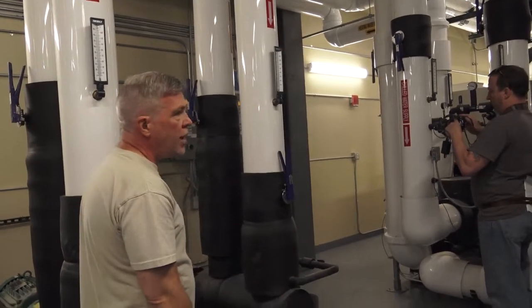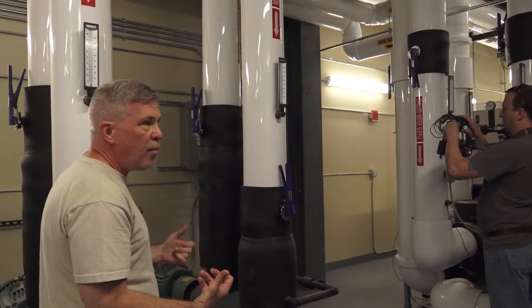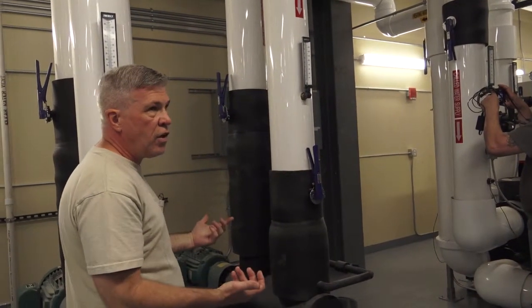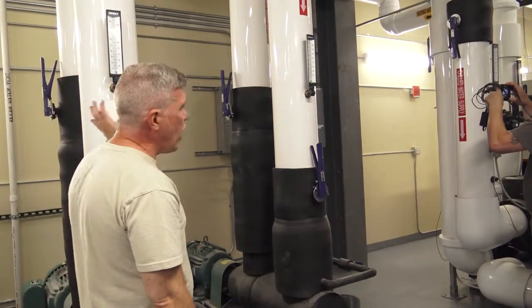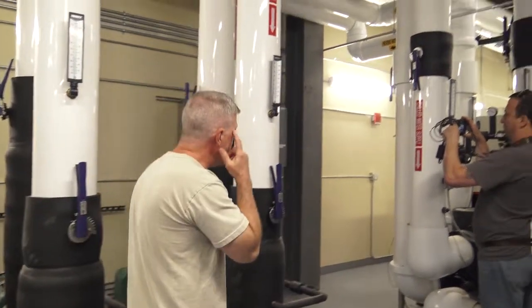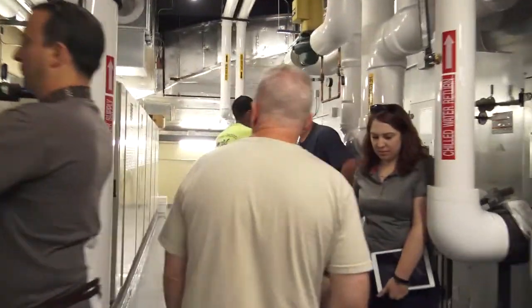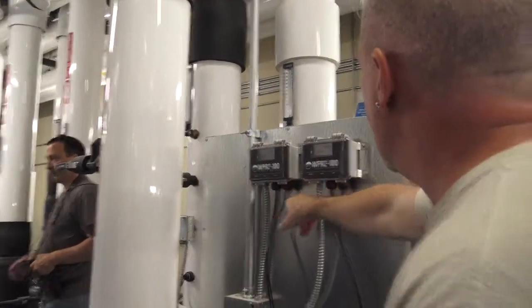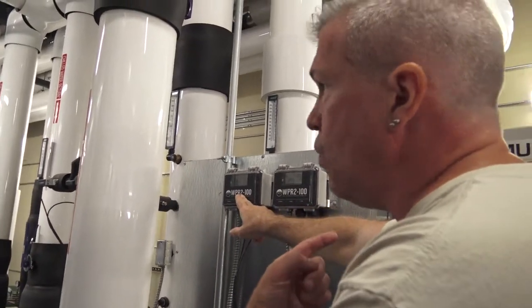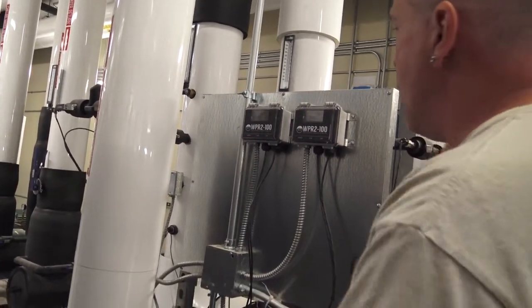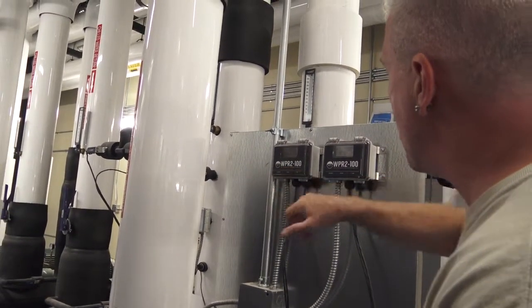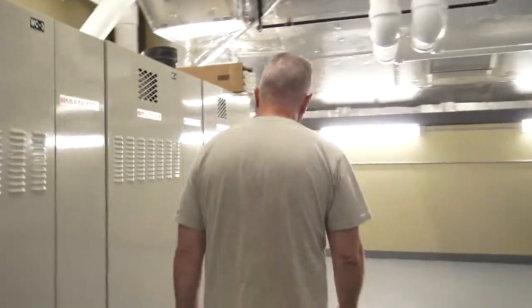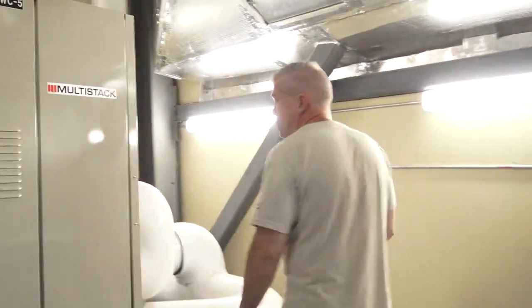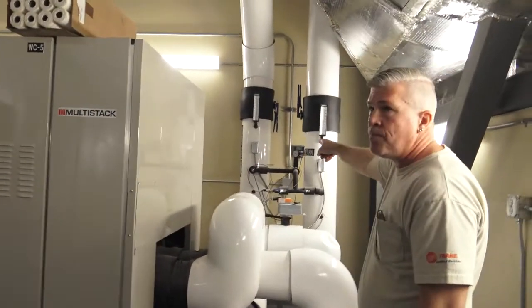So if you have a pump that isn't running, the drives have alarms that will generate from it if it fails out, or if the drive itself is in failure, you'll get an alarm. They all run off of differentials. Most of them are the ones that are up here. So you got your chill water differential that's controlling the chill water side. Now these are all what's entering or leaving the multi-stack. So chill water differential to the multi-stack, hot water differential, and then the geo one hanging down from the corner here. So it's the one straight back on the wall.